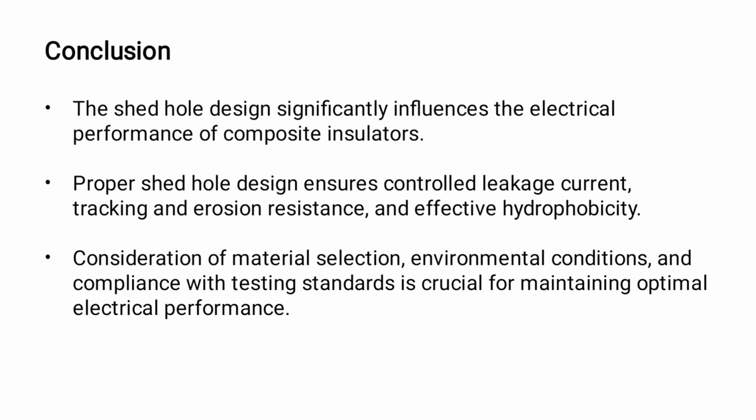Conclusion. The shed hole design significantly influences the electrical performance of composite insulators. Proper shed hole design ensures controlled leakage current, tracking and erosion resistance, and effective hydrophobicity. Consideration of material selection, environmental conditions, and compliance with testing standards is crucial for maintaining optimal electrical performance of the insulators.